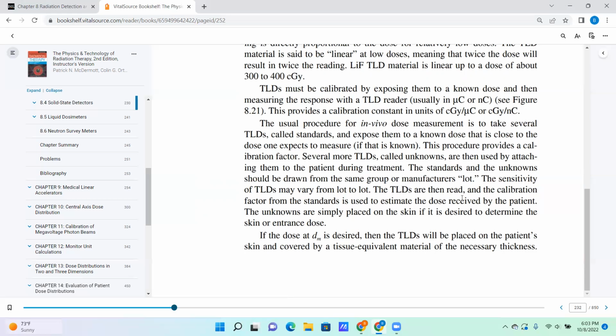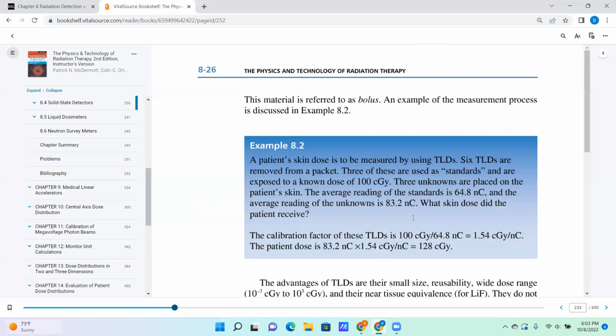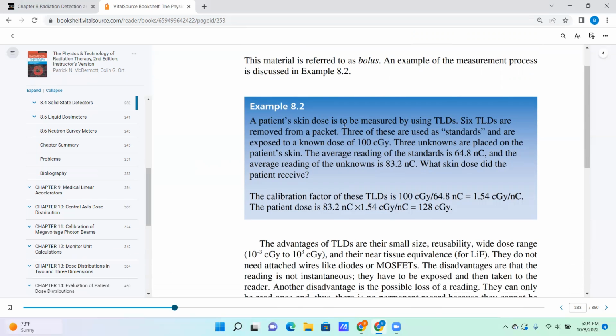The TLDs are then read, and the calibration factor from the standards is used to estimate the dose received by the patient. The unknowns are simply placed on the skin if it is desired to determine the skin or entrance dose. If the dose at Dmax is desired, then the TLDs will be placed on the patient's skin and covered by a tissue equivalent material of the necessary thickness. And that's referred to as bolus. An example of the measurement process is here in example 8.2.